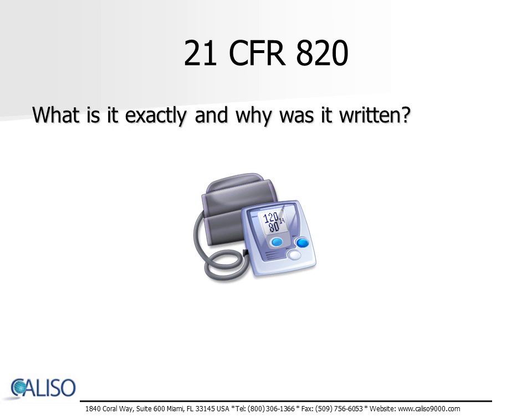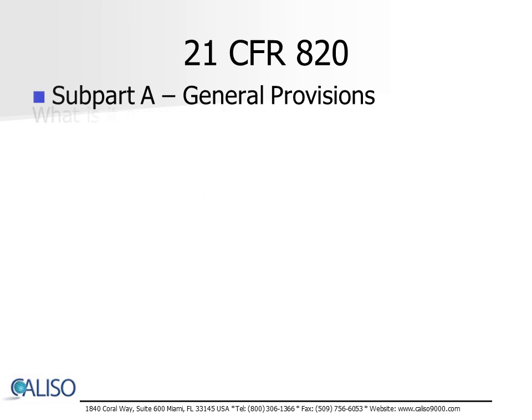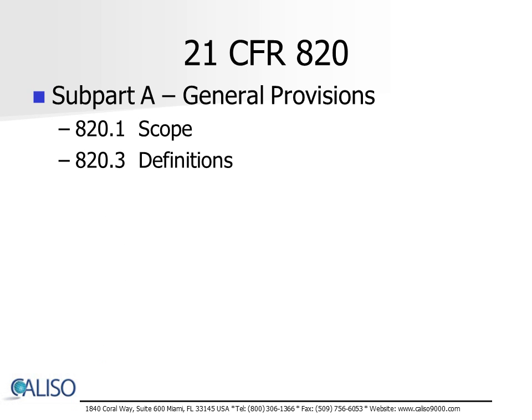And by monitor, I mean how complaints are handled. The sections of 21 CFR 820 are as follows. Subpart A, General Provisions, which doesn't contain any requirements, but includes the scope, definitions, and a brief description of what a quality system is.